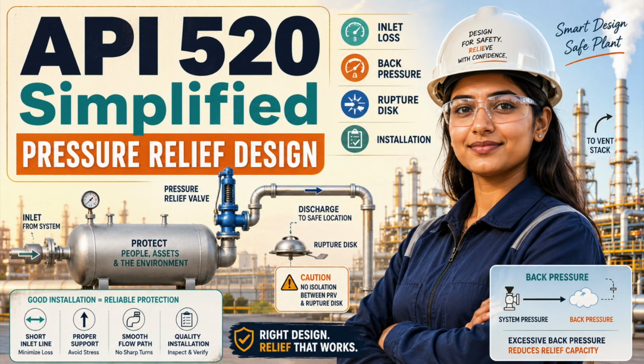Now move upstream to the inlet piping, where one of the most common failures begins. Excessive inlet pressure loss can destabilize a relief valve. The valve opens, flow increases, pressure at the valve inlet falls, the valve begins to close, pressure recovers, and the valve reopens. That rapid cycle is chatter.